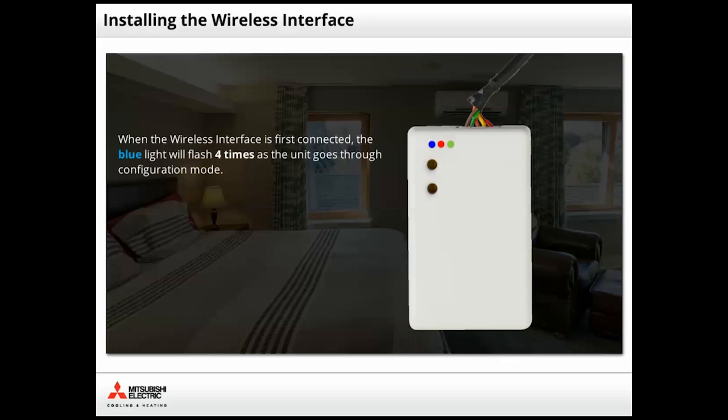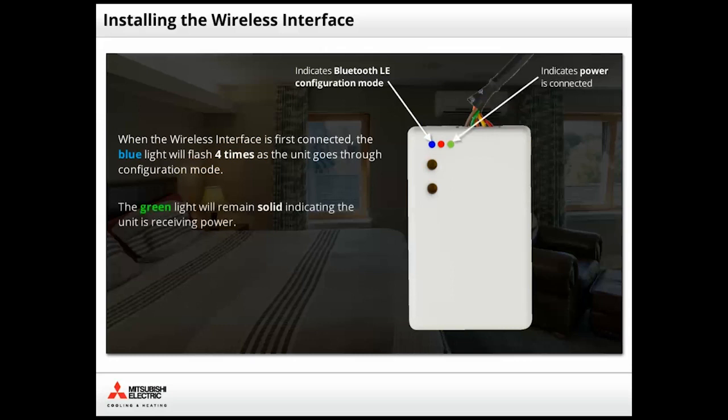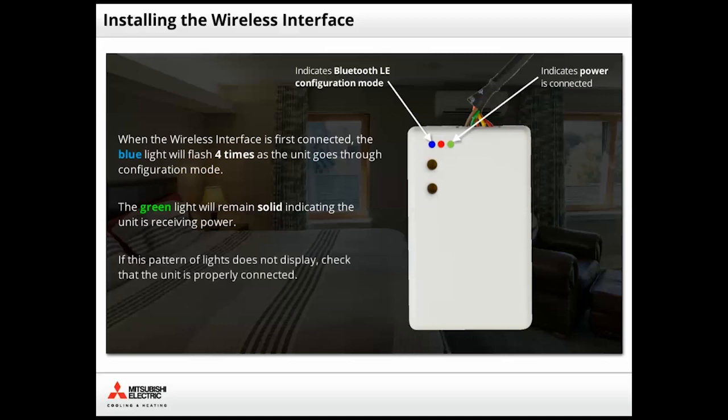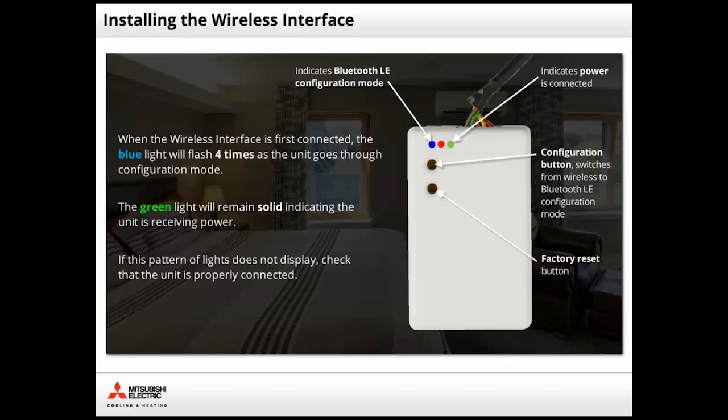The blue light will blink four times, indicating the interface is communicating and going through configuration mode. The green light will illuminate, indicating that the unit is receiving power. If you don't see this pattern of lights, check to see the connector is pushed all the way in. There are two buttons on the wireless interface, configuration and factory reset. You will not need to press either of these during installation.